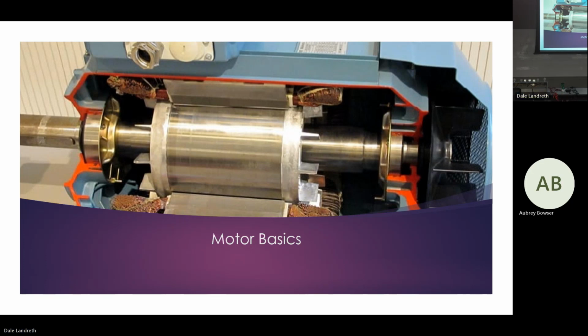It says this condition decreases conductor impedance, basically resistance, total resistance, to the point that it is effectively a short circuit. So if we got a short circuit, what do amps do? They go up. So now the rotor's stopped, it's at locked rotor amps, and we know if we put our amp clamp on it, that stator is going to be pulling high amps. So the rotor's not turning.